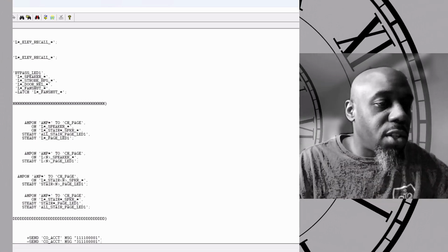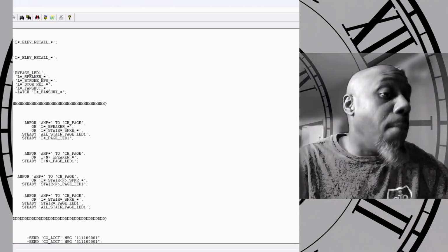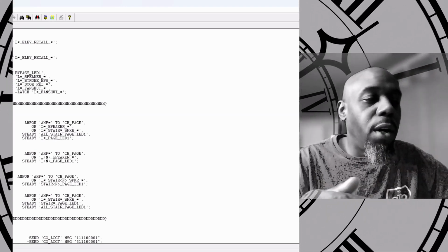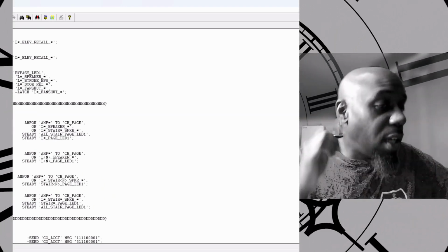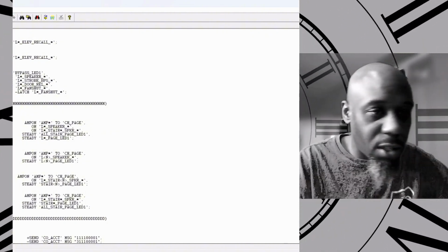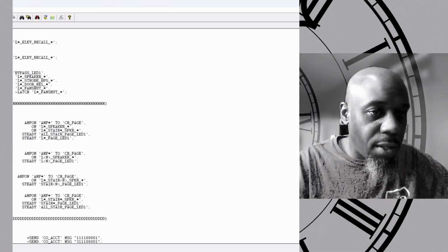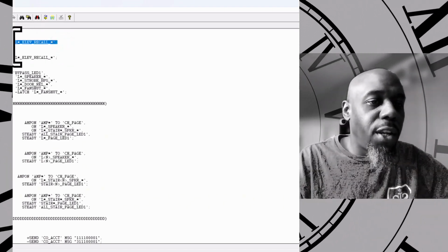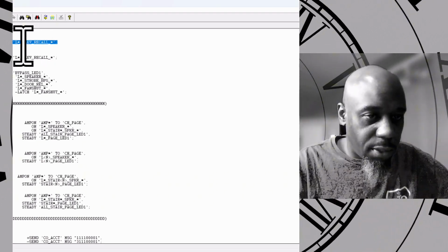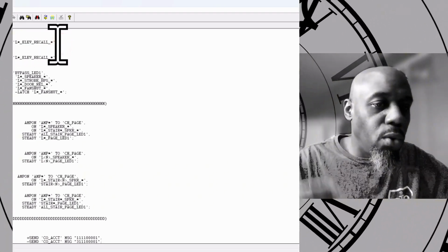So these asterisk stars are wild cards. So essentially this is telling me that there are more than one. So it could be L1, auto, elevator, smoke 1, or something like that. We're going to go to the objects and see exactly what this message label is. And you need this semicolon right here to divide the input statement and also the output statement. Now on the output side, they're turning on a relay. It's an elevator recall relay, and they have a semicolon to end the rule equation.